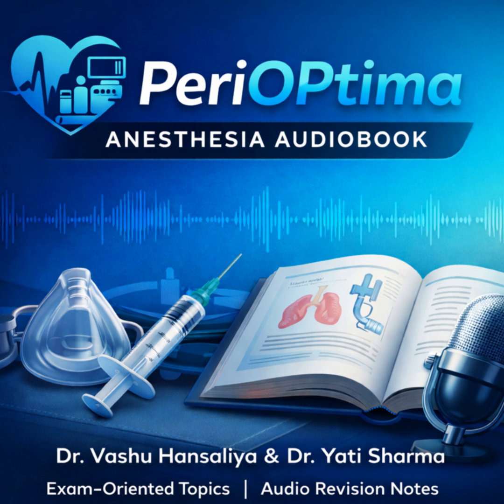So the reservoir is exactly what it sounds like, a holding tank. It gives the perfusionist a buffer of fluid volume to manage shifts in the patient's blood pressure. Where does it go from the tank? From the bottom of the reservoir, the blood is aggressively pulled by the main arterial pump. Historically, these were roller pumps, but modern circuits often use centrifugal cones. This pump generates the massive driving force required to push the blood through the rest of the high-resistance circuit.